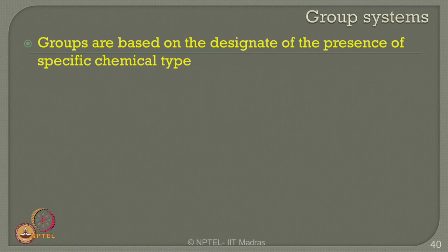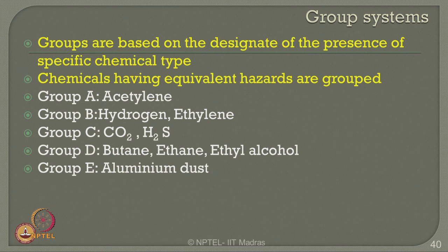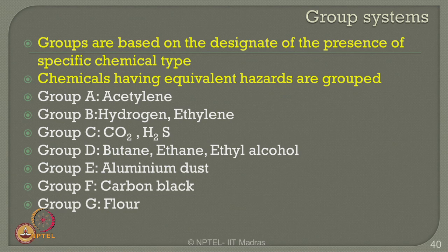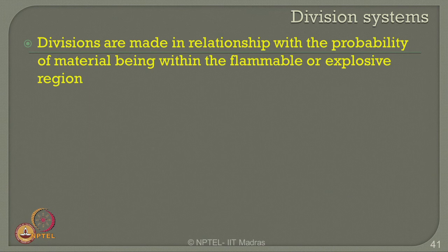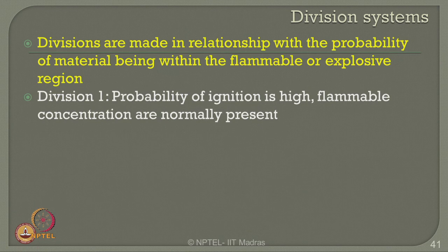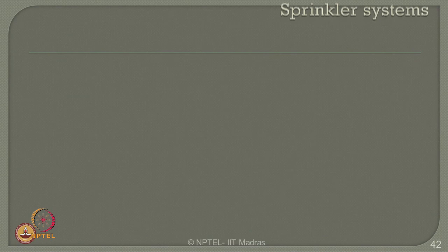Groups are based on the designation of specific chemical types: Group A is acetylene, Group B is hydrogen and ethylene, Group C is carbon dioxide and hydrogen sulfide, Group D is butane, ethane, and ethyl alcohol, Group E is aluminum dust, Group F is carbon black, and Group G is flour. Division systems as recommended by OSHA guidelines are based on probability of material being within the flammable or explosive region. Division 1 indicates probability of ignition is very high and flammable concentration is normally present. Division 2 indicates hazard only at abnormal conditions, with flammable materials normally contained in closed containers.